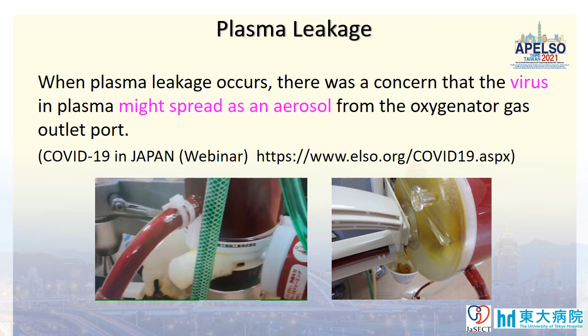Many facilities seem to take measures for plasma leakage because it was introduced in the webinar held last year that there was a concern that the virus in plasma might spread as an aerosol from the oxygenator gas outlet port. I'm going to introduce papers and methods for ECMO management in our journal.